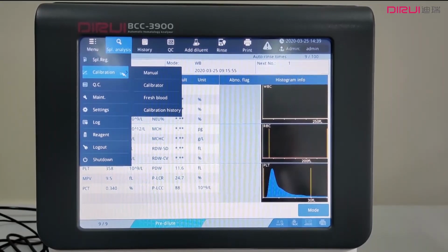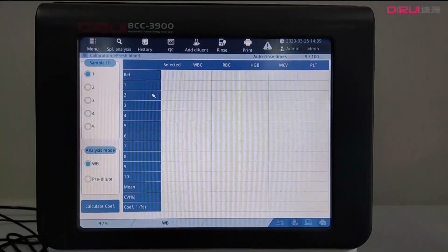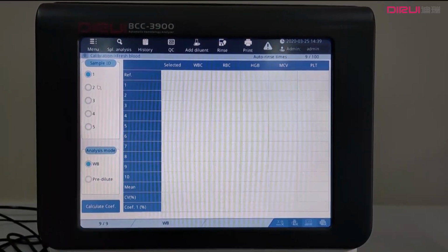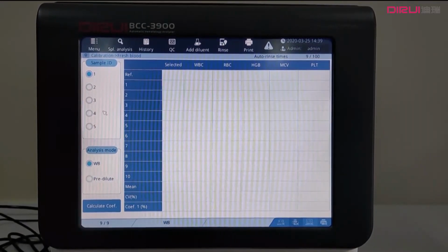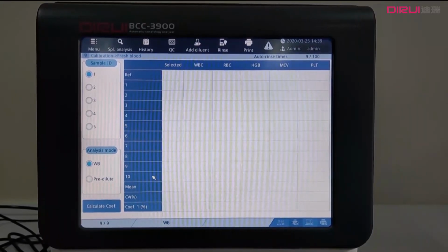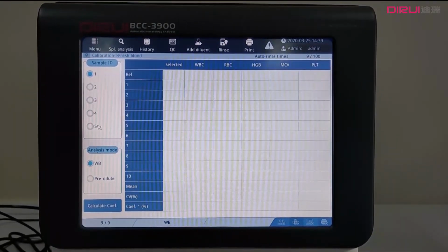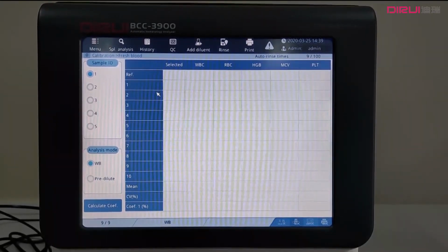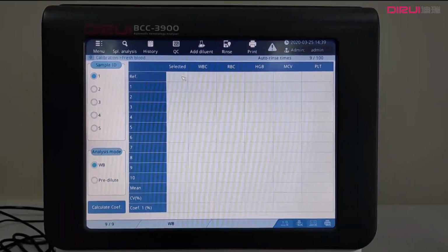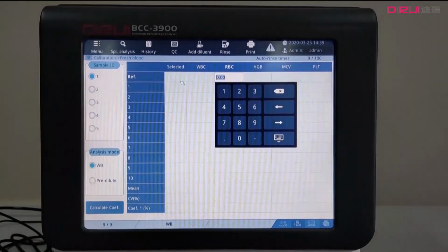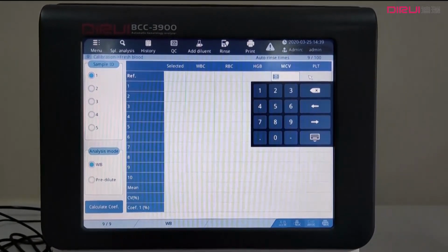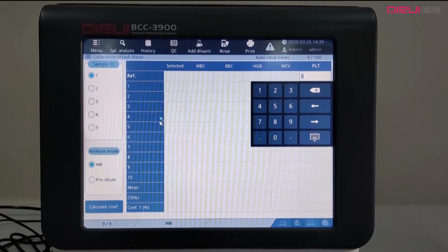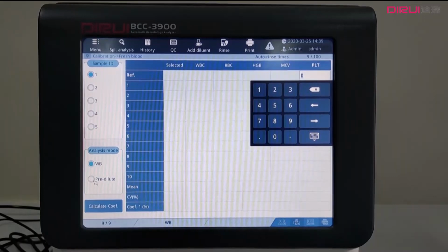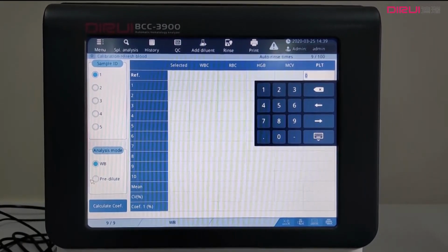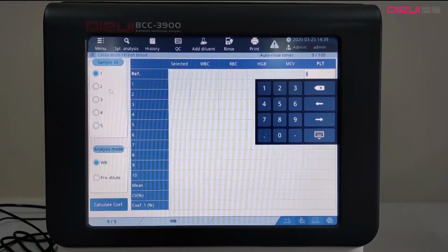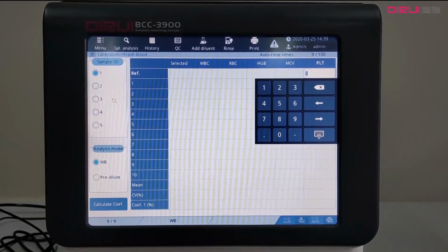Another way of doing calibration is fresh blood calibration. Go to menu, calibration and fresh blood. In this interface, there will be 5 different samples and each sample will be tested 10 times. Make sure all of these samples have been tested on another machine with accurate results. Those results will be registered here in the reference tab. Here all of the results will be added and will be checked under WB or pre-diluted mode according to your choice. So please make sure all of the samples have been checked on another accurate machine.